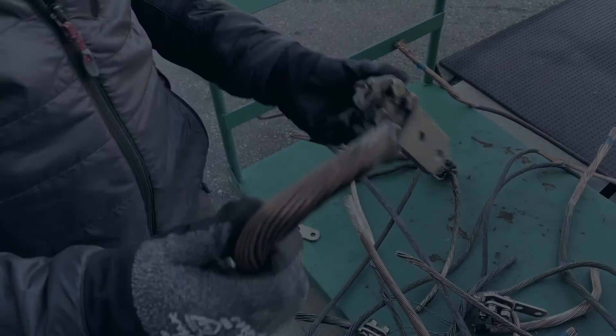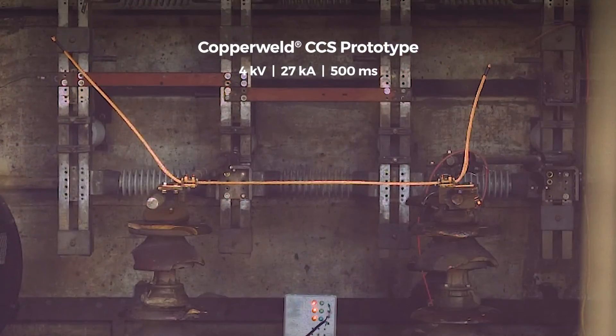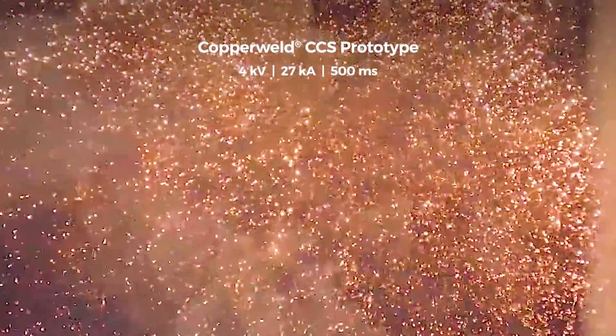When we returned to the test lab, we left with more questions than answers again, but the newly adjusted KF values had predicted the results pretty well for the range of CCS conductors used in substations, and the path ahead was clear.